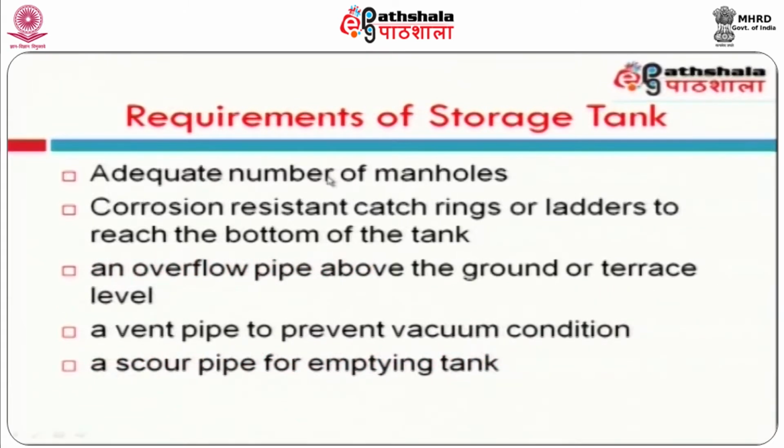The first one is the number of manholes. In order to provide access for cleaning, repair, etc., manholes are necessary on the cover or roof of the tank, and you must have steps or ladders to go into the tank that must be corrosion resistant, and an overflow pipe from the maximum water level which will flow to the ground or terrace, a vent pipe in order to prevent vacuum. This is an important arrangement.